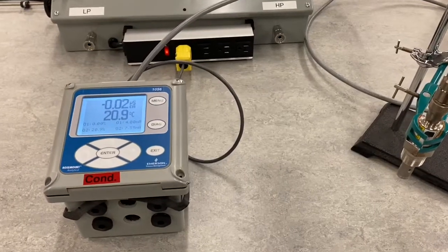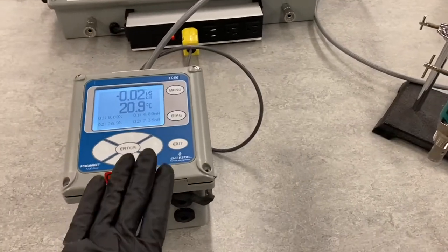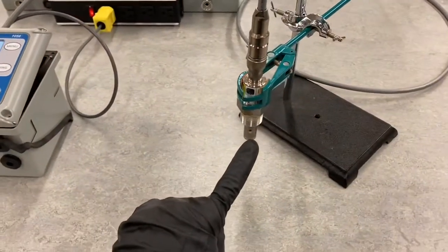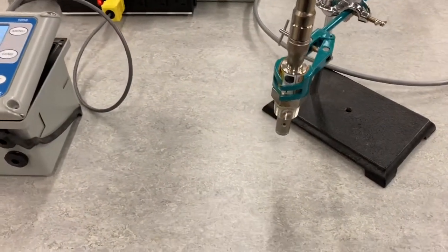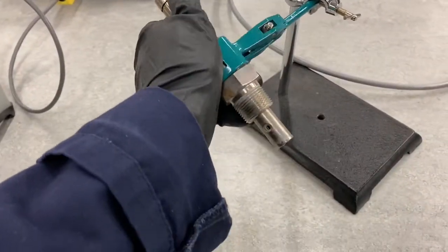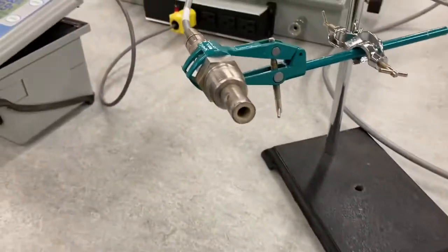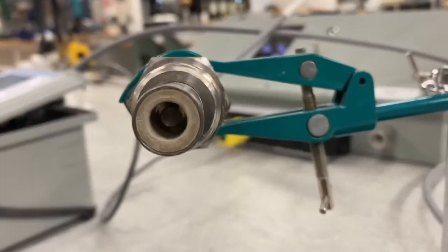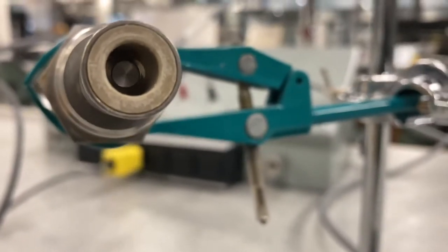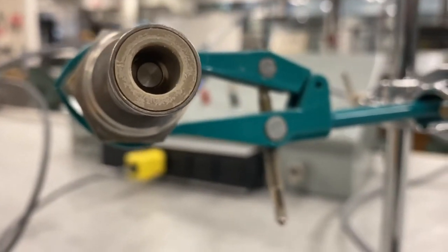This is the 5th lab of this course. We're using our Rosemount 1056 again here, but this time we have a conductivity probe connected to it. This is a 2 electrode probe. Let's see if I can focus this. There we go.